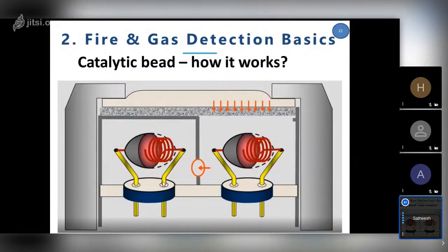Catalytic bead, how it works basically. You can see here, there are two beads. Basically, the bead is nothing but platinum wire, wired to the electronics. The electronics gives a small current so that the bead is at high temperature. There will be combustion happening inside the gas sensor itself. When there is a gas leak, the gas enters here. Some gases can cool down this bead, some gases can increase the temperature. So this will contribute a resistance change.